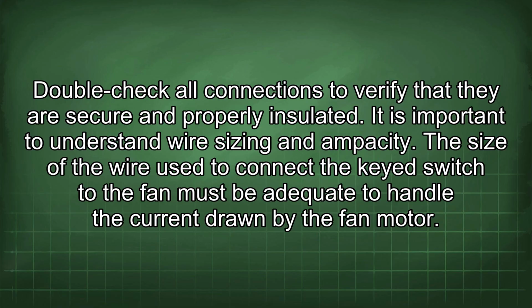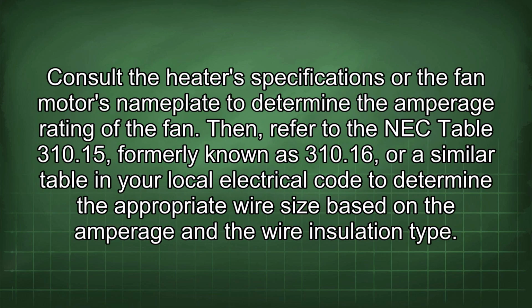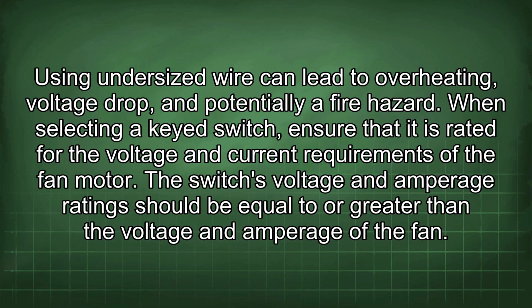It is important to understand wire sizing and ampacity. The size of the wire used to connect the keyed switch to the fan must be adequate to handle the current drawn by the fan motor. Consult the heater's specifications or the fan motor's nameplate to determine the amperage rating of the fan. Then, refer to the NEC Table 310.15, formerly known as 310.16, or a similar table in your local electrical code to determine the appropriate wire size based on the amperage and the wire insulation type. Using undersized wire can lead to overheating, voltage drop, and potentially a fire hazard.